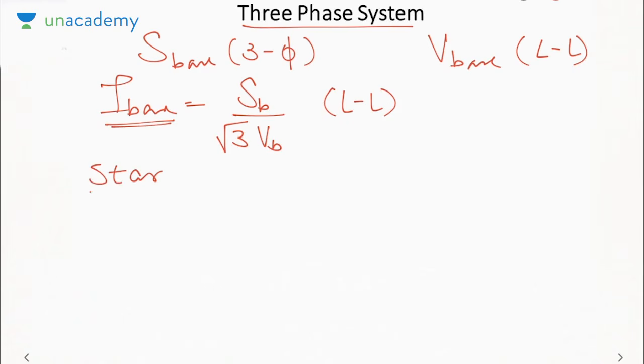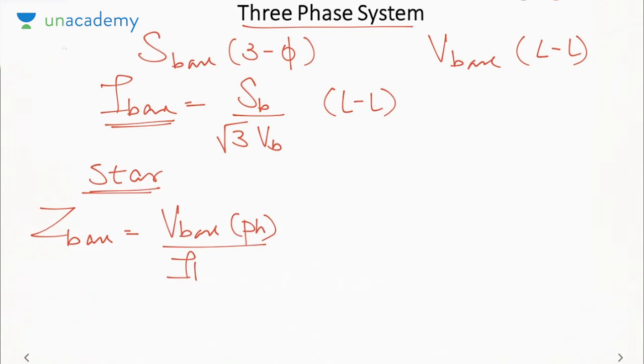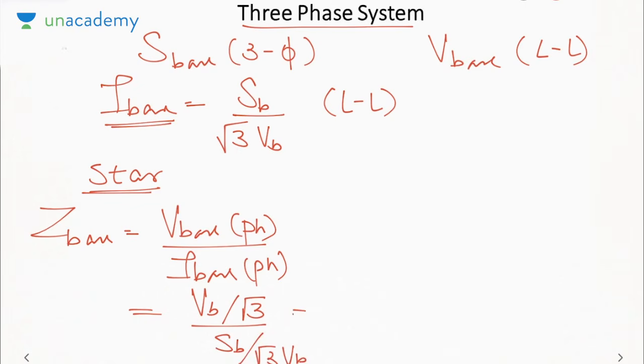One is for the star connection. Z base will be V base in one phase, because impedance is connected in each phase, over I base in phase. Now in star we know phase voltage is equal to line voltage by root 3. So that is V B by root 3. But in star connection, phase current and line current are the same, so S B by root 3 V B. So this will be V B square by S B, the same as the single phase system, that is for a star connection.